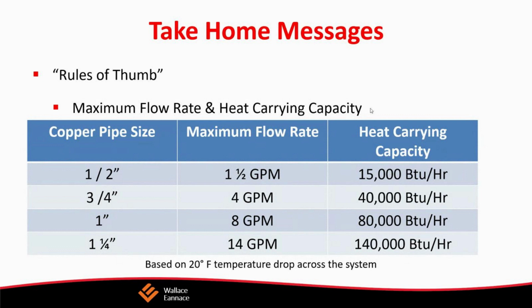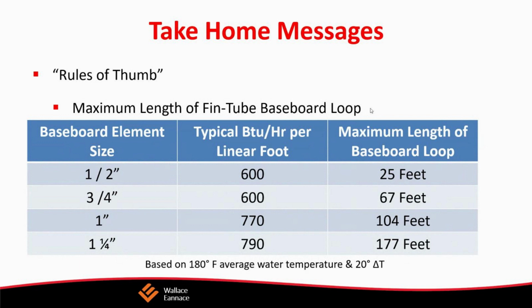That's how I determine the flow rate for the boiler, and also by the heating load. If I have an air coil, a heating coil which produces 40,000 BTUs, then I know I'm going to need a flow rate of 40,000 divided by 10,000, which is 4 GPM. So that is a really key point. If you get anything, you want to bring that home.